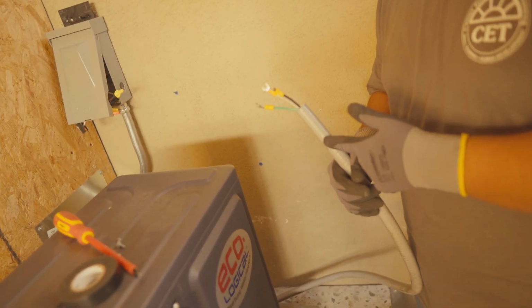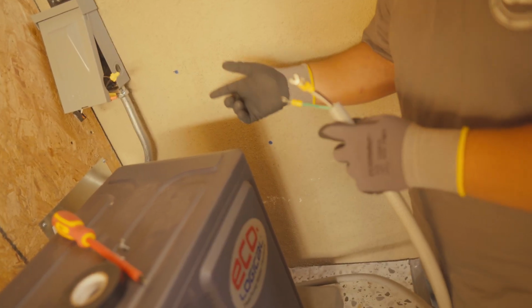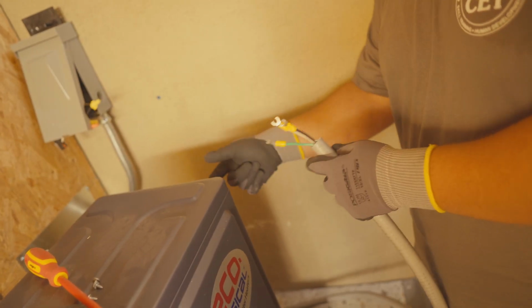Run the electrical lines from the junction box to the outdoor condensing unit, making sure the conductors are properly rated and installed according to local electrical codes. Secure all connections, including the ground wire, to ensure safe and stable operation.